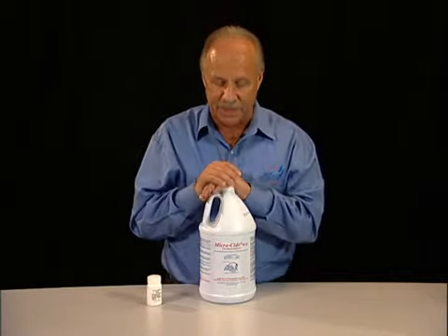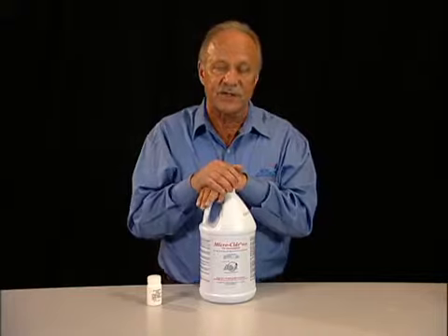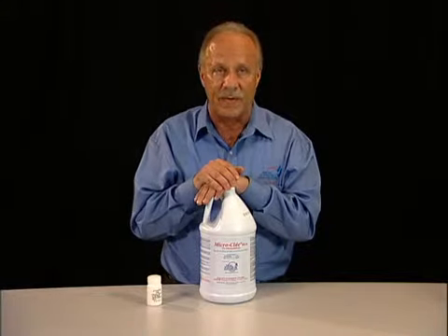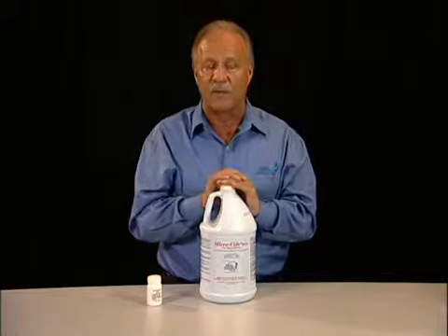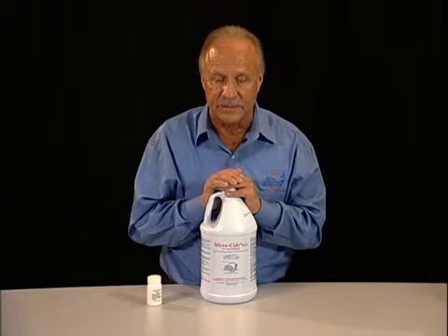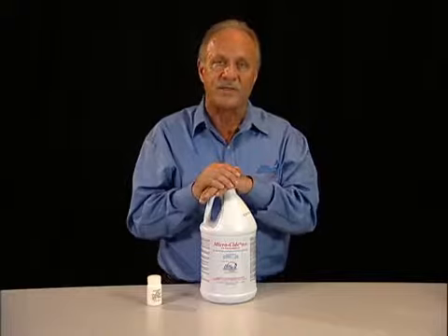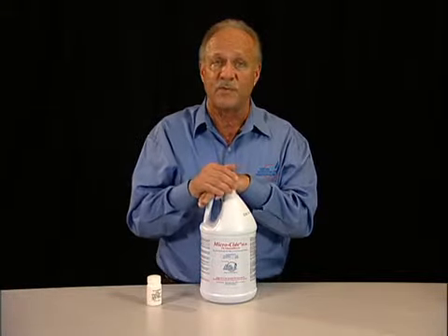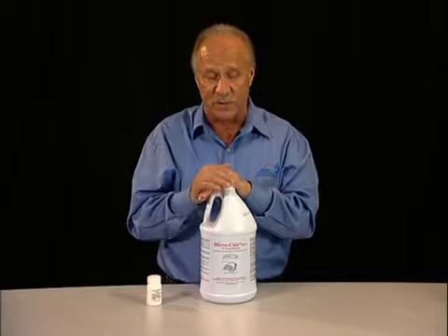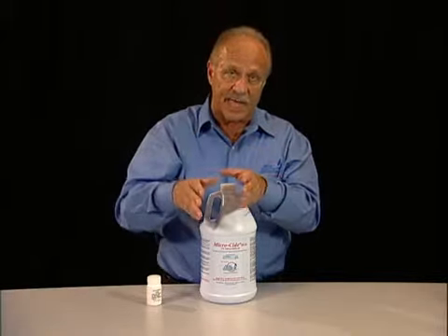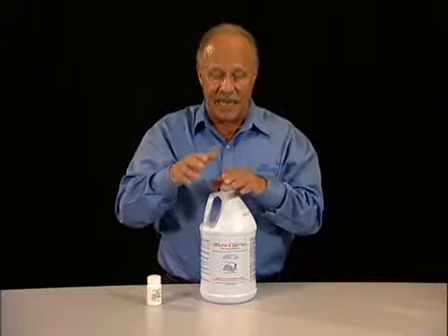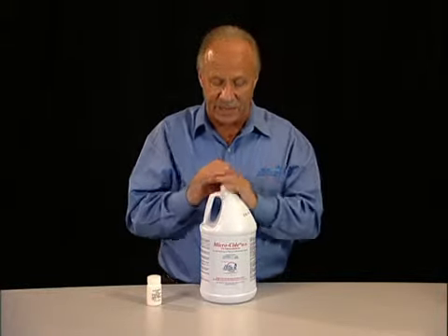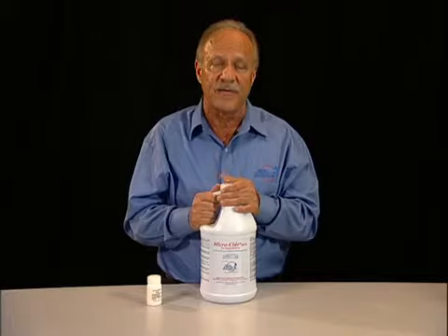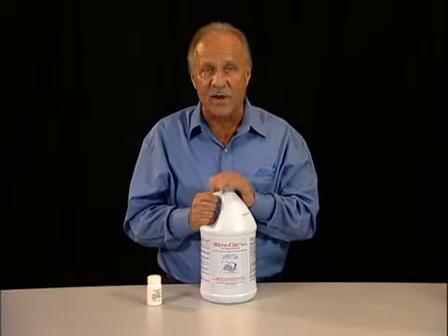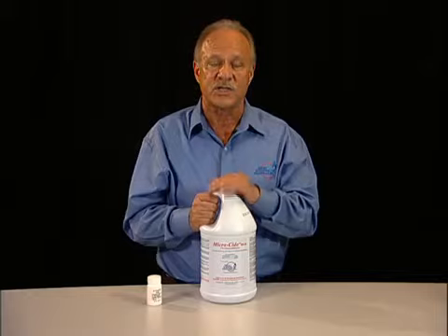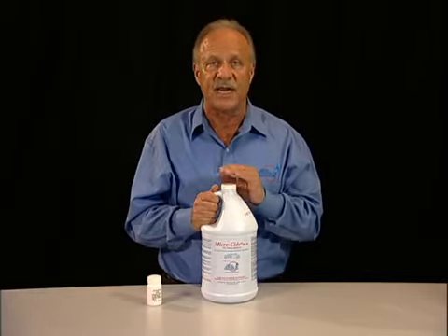At the conclusion of the soaking of instruments in any glutaraldehyde, whether it be a Metricide product, whether it be this product, or whether it be a Cidex product, it requires that you take your instruments and put them through a triple sequential rinse, where you first rinse the instruments, rinse them again, and then in a separate container rinse them again in order to remove the glutaraldehyde from the surface. As I said, this is a very simple, easy to use product. It works very quickly, and it accomplishes what your customer is looking for, and that is high-level disinfection in less than a half an hour.